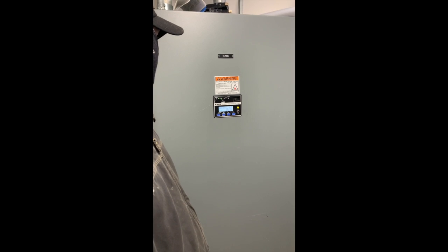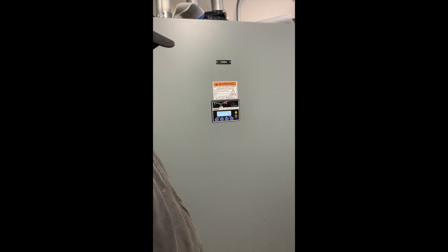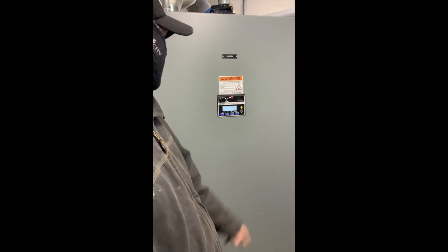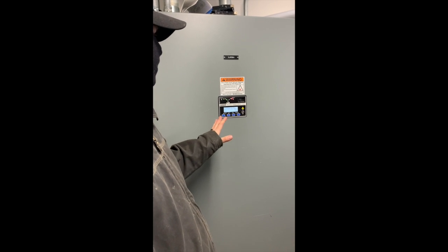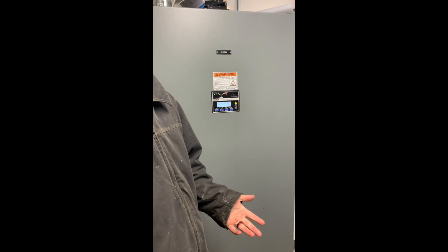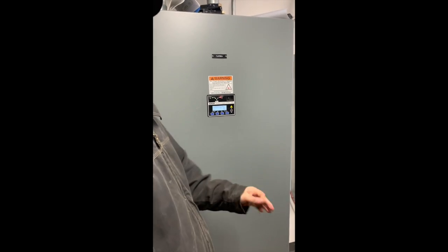So you can hit start. Boom, the generator starts and runs. You get your red indication saying emergency power is available, and your emergency voltage from the generator side shows up. Then say I ran it for however long you wanted and I'm happy. Usually, BAAQMD, they're sticklers. They want us to run these minimally, usually about 5, maybe 10 minutes, probably because of air quality control.